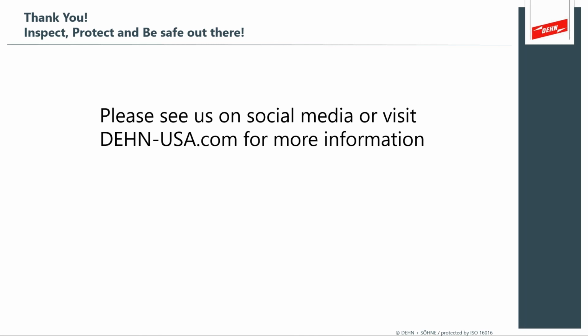For an AC powered surge protection device, the only way to know for sure is to remove it from the AC service, get it on a bench, and apply a particular voltage controlled and current limited power supply, then measure the device to see if it's still within its manufacturer's spec. It still doesn't tell you how much longer it has to live, but it tells you if it's within its manufacturer's recommendations. The only way I've found to do that is to pull it out of service and put it on a bench with an appropriate voltage source with current limiting, because you want to drive the SPD into its performance range.